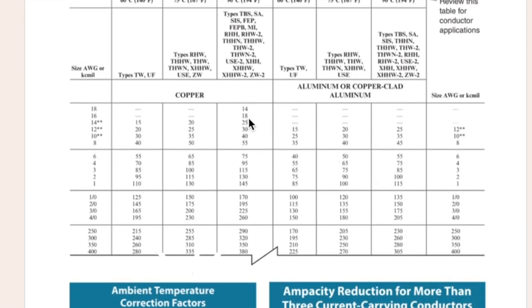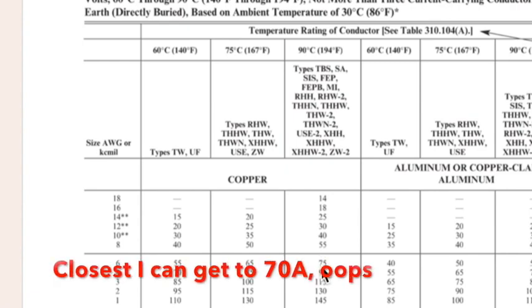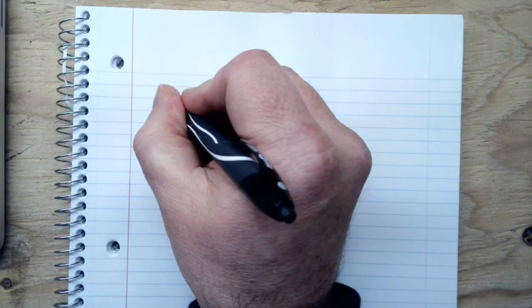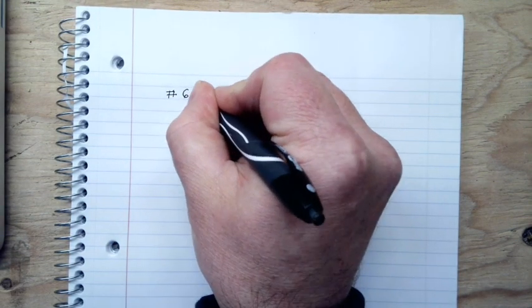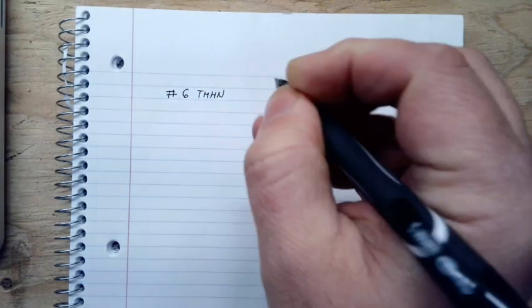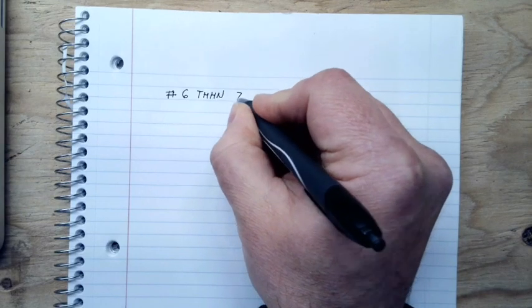The first thing I need to know is I'm looking for THHN copper and that it's got to be rated for 70 amps. So I'm going to come up and look for my THHN. I'm in copper, I'm in THHN, so I'm going to scroll down, and 75 is the closest I can get without going too crazy. So 75 amps will be a number 6 wire. So now over here I'm going to write number 6, THHN. And then that is good to 75 amps.